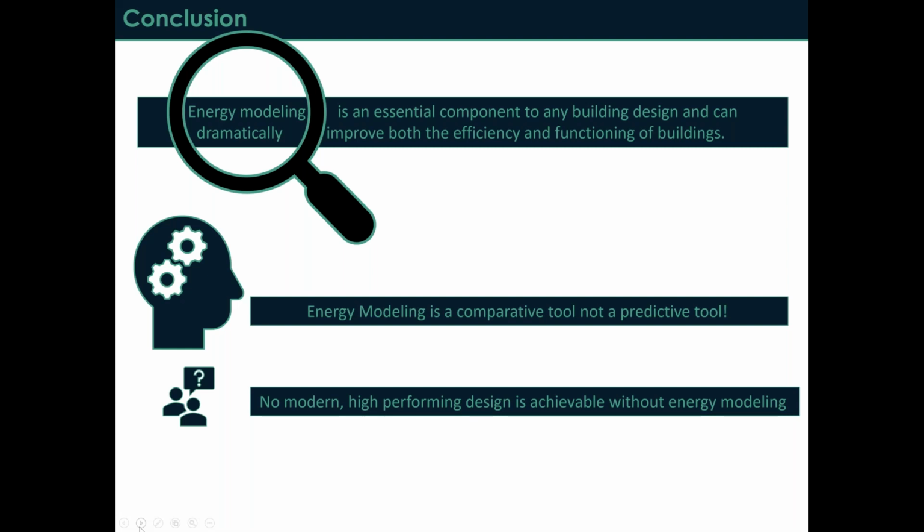Energy modeling is an essential component to any building design and can dramatically improve both the efficiency and function of the building. Also, energy modeling is a comparative tool, not a predictive tool. This is one thing that I want to say, that some people confuse it with measurement and verification.